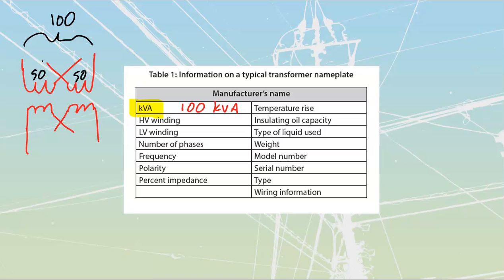There is also, when we look at the kVA, they're going to give us voltages, but they're not going to give us current. The reason for that is the only thing that controls the amount of current delivered by a transformer is the load. If they put the current on there and then you hook up only a small little load onto that thing, then it's not going to be pulling that amount, right? So it's going to be up to you as the transformer to be able to take that kVA, divide out your voltage, and figure out your amperage ratings from it.